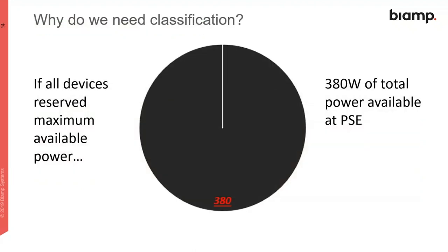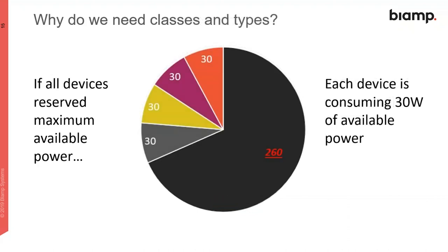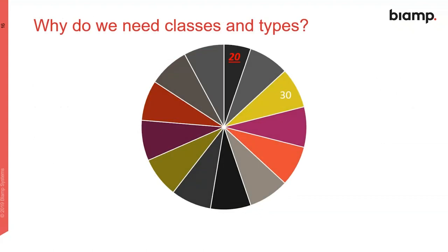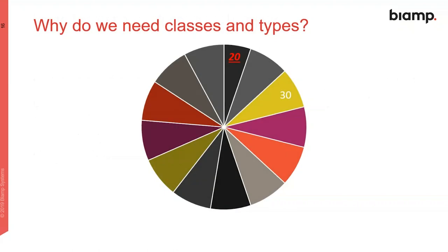So what's the point of all these classes and types? We want to be efficient in using our power, so we want devices to only consume or only ask for how much power they need. If we look at an example of a switch with a budget of 380 watts total, and let's say all devices were allocated the maximum of 30 watts, we could only have a certain number of devices - that limit is 12 at this point - and we'd have 20 watts left over.